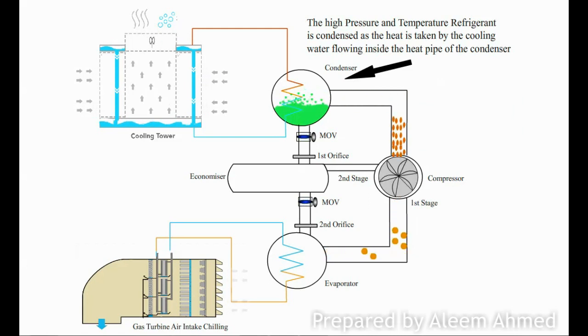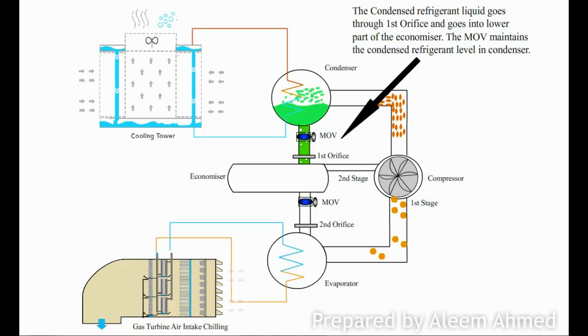The condensed refrigerant from the condenser goes through the first orifice to the lower part of the economizer. The condenser MOV maintains liquid refrigerant level in the condenser.